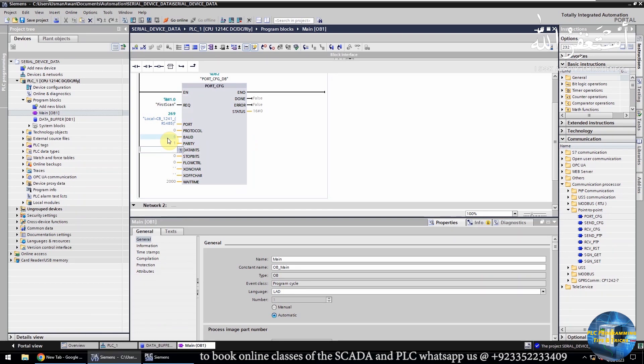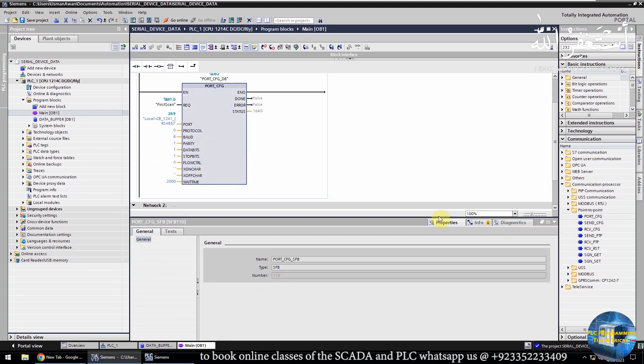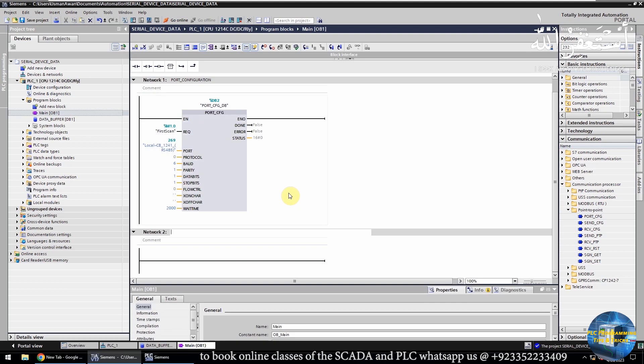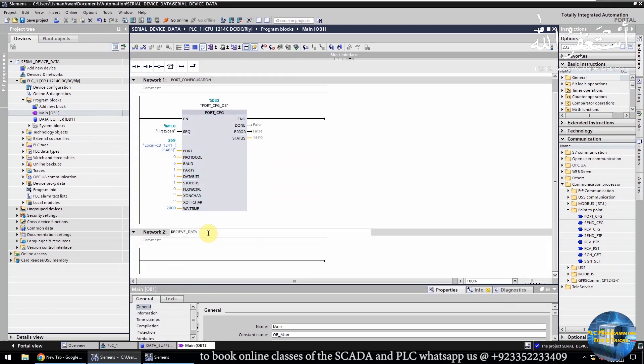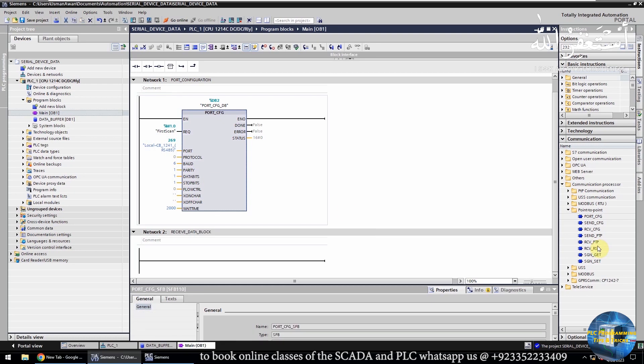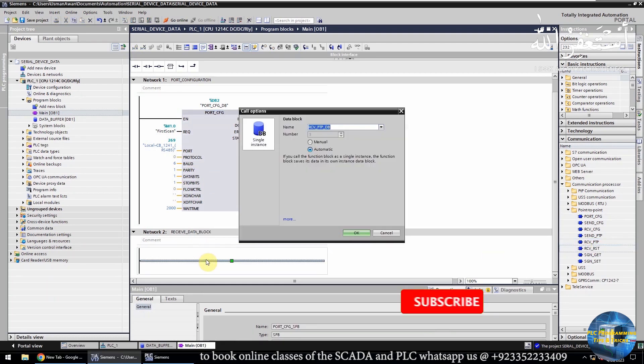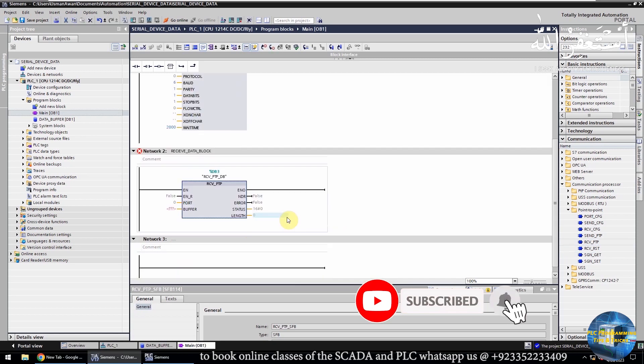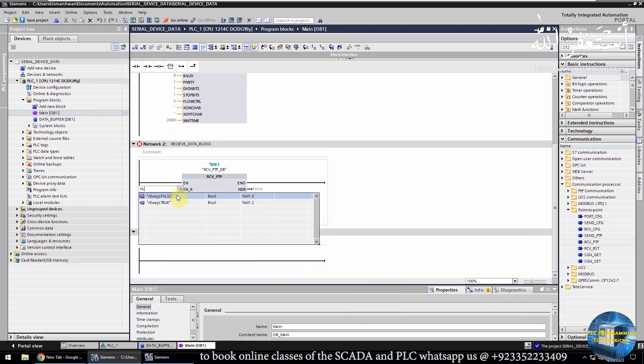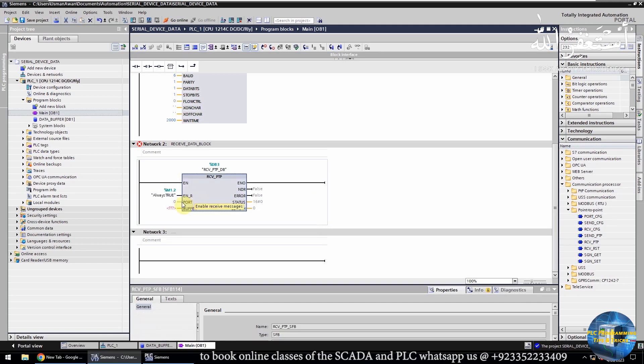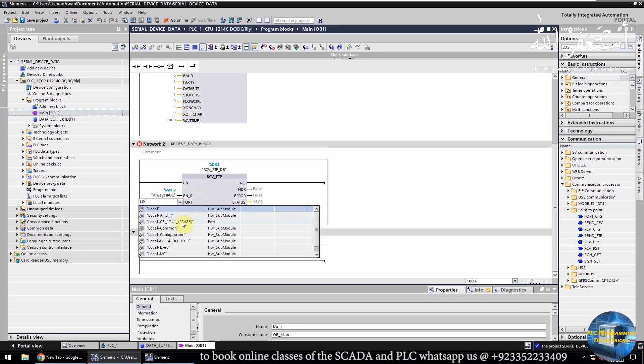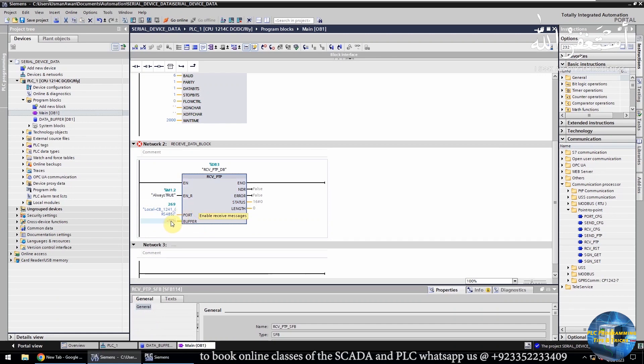Next, we will enter 1 in the data bits field, which means 8 data bits. Then we will enter 1 in the stop bit field, which means 1 stop bit. The rest of the inputs we can keep as they are. In network 2, we will make logic to receive data from the RS-485 port. We will drag and drop the receive PTP function on the ladder. We will insert the always true bit in the enable input of the receive function, which will keep the receive function always enabled. Then we will enter the local port number 269 to start receiving data from the RS-485 port.